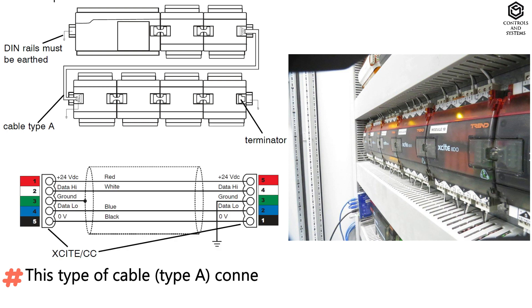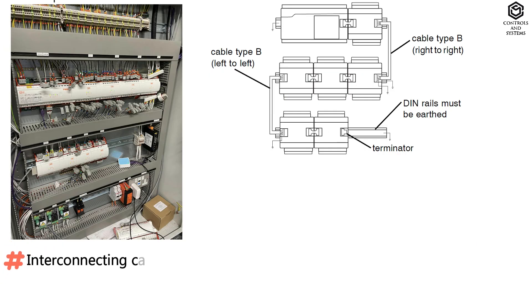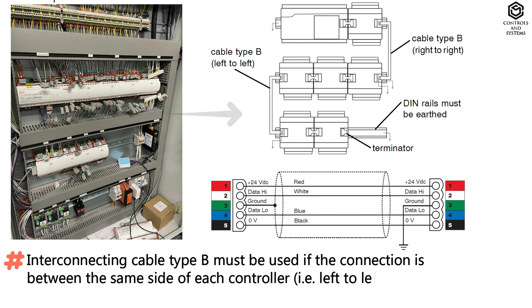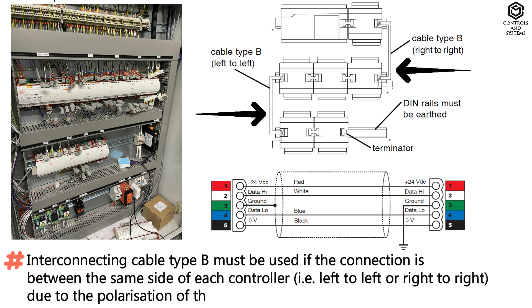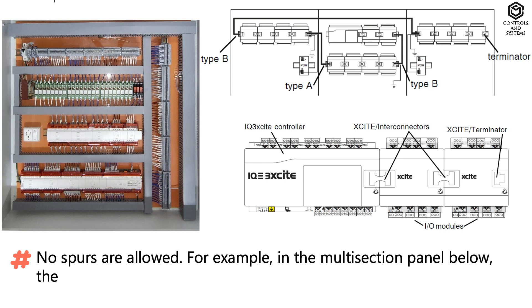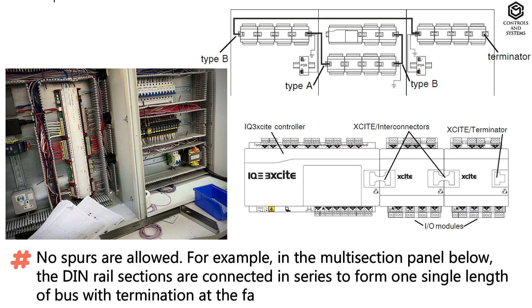The cable core colors shown are for the recommended Belden 3084A cable. Cable type A connects the right-hand side of one module to the left-hand side of another. Interconnecting cable type B must be used if the connection is between the same side of each controller — that is, left-to-left or right-to-right — due to the polarization of the connectors. No spurs are allowed. For example, in a multi-section panel, the DIN rail sections are connected in series to form one single length of bus with termination at the farthest end from the controller.